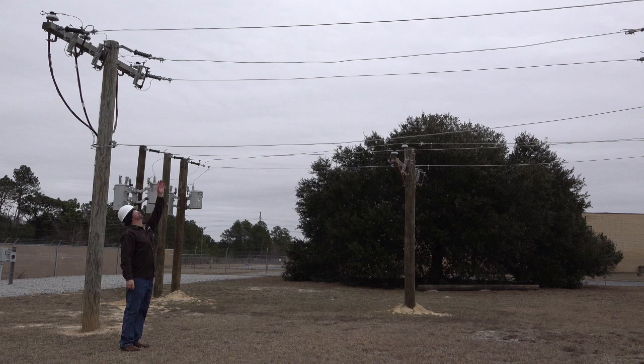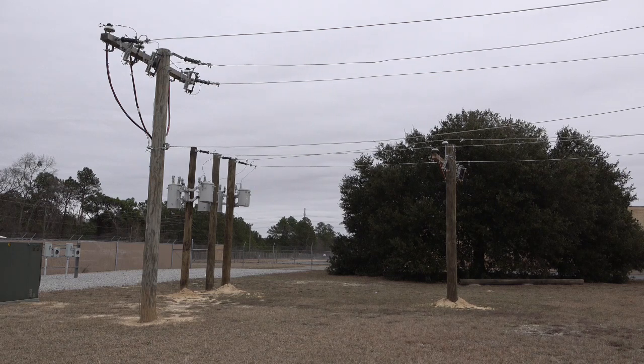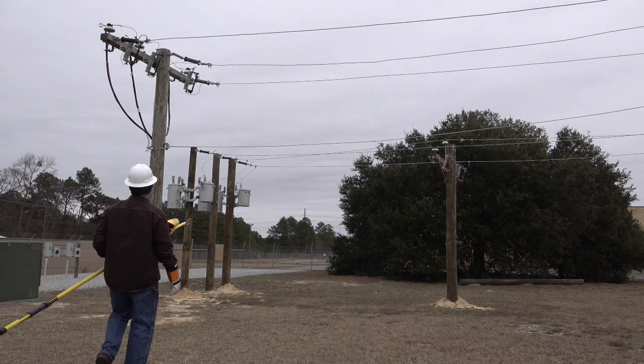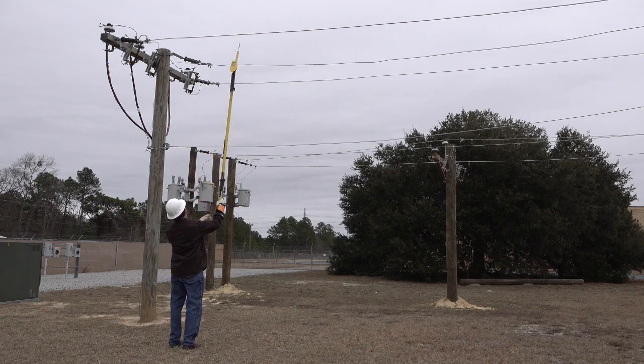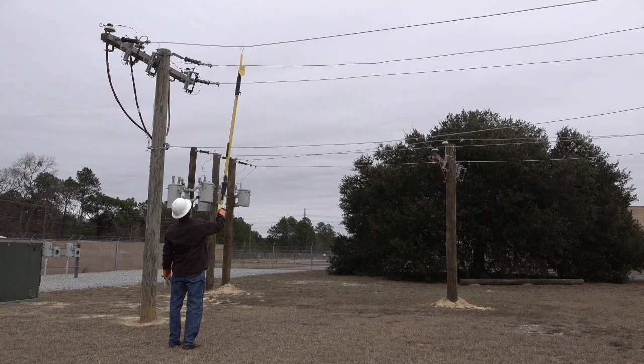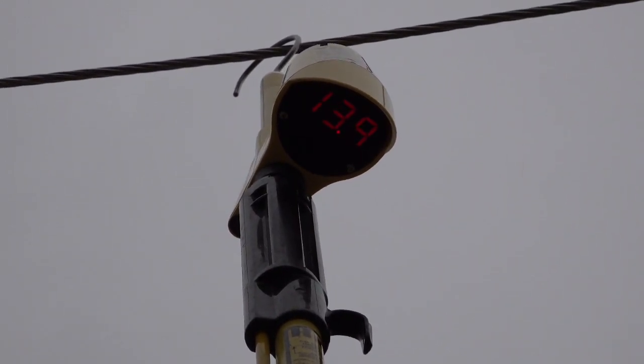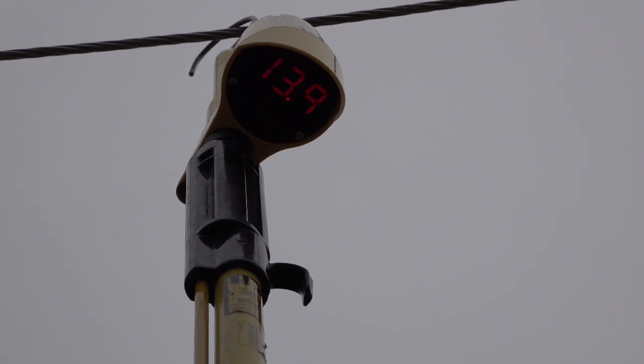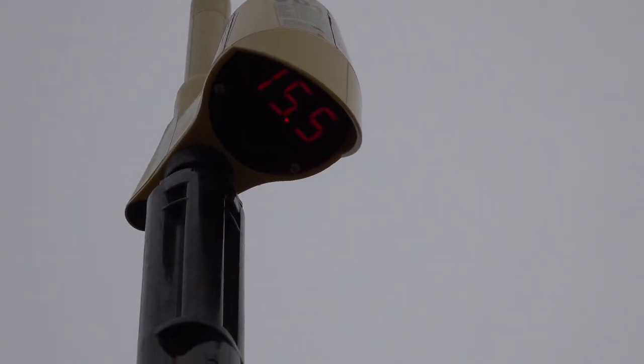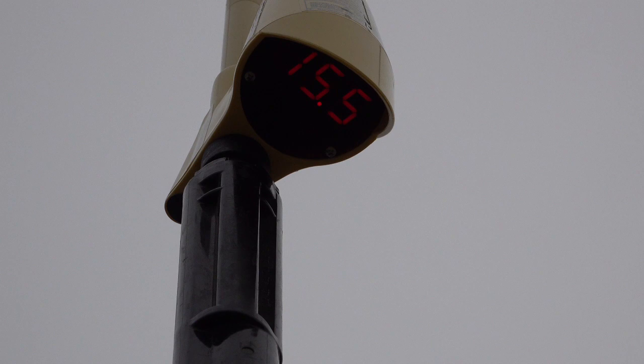Remember, all single probe devices have to capacitively couple to Earth in order to achieve a voltage display. Since the distance I am now going to work is greater than the distance it was at the pad mount transformer, I must now internally calibrate the meter by changing the switch position to compensate for that distance. So now with the meter in the OH switch position, let's hang it on the outside phase and see what the meter reads. Hanging on the outside phase, notice the nominal voltage reading is roughly 14 kV. Now let's see what happens if we hang the VD1000 right above the neutral wire on the center phase. Notice the reading is approximately 1.5 kV higher.